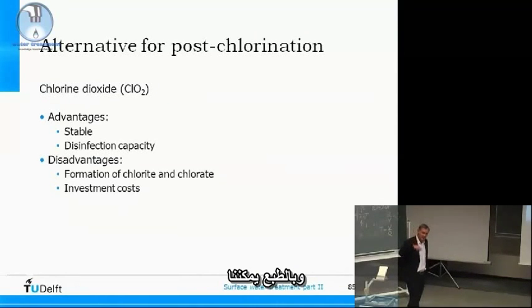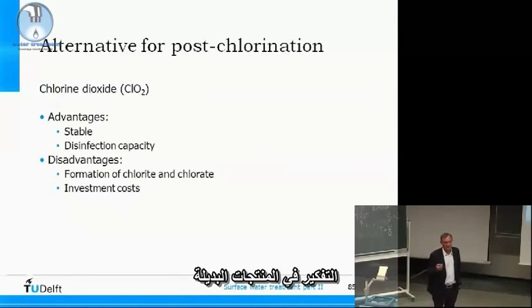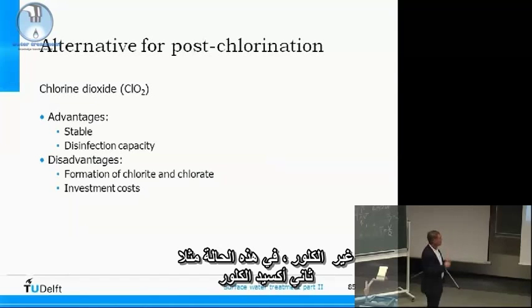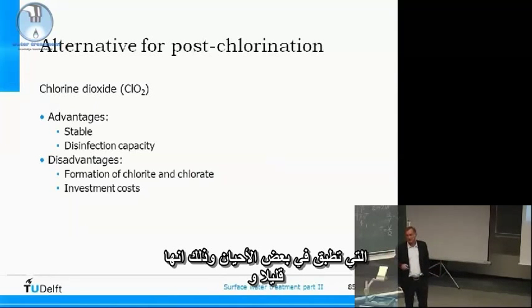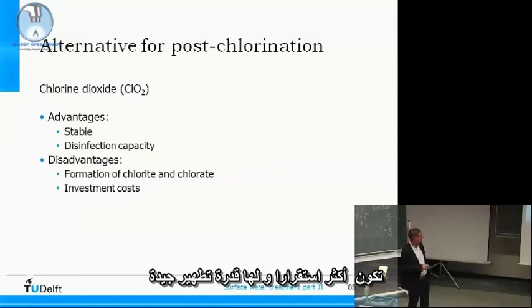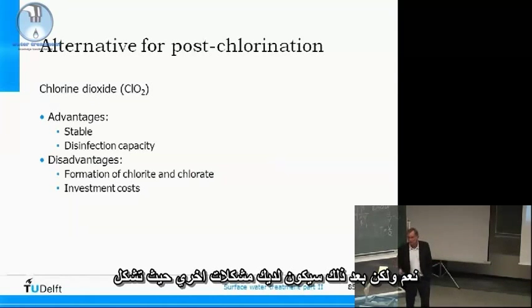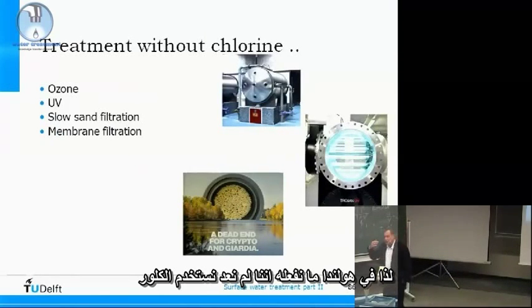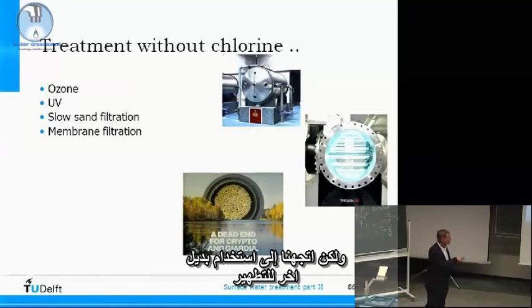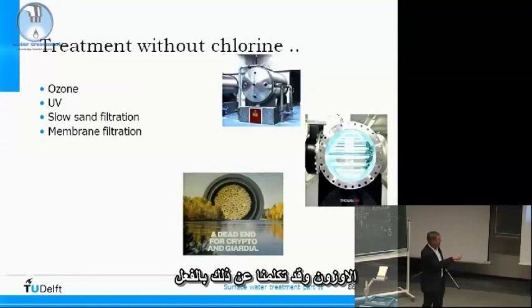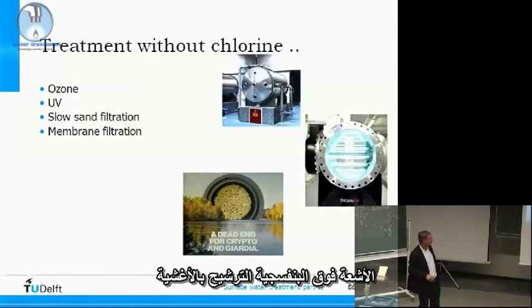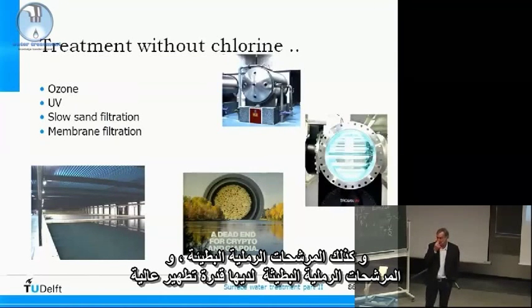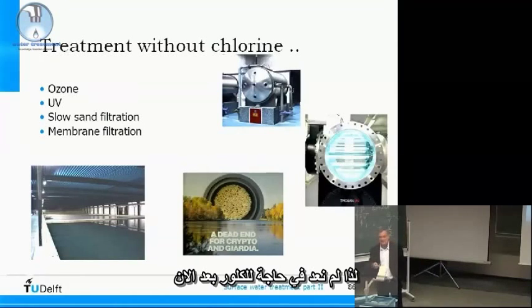There are also alternative products to chlorine. Chlorine dioxide is sometimes applied — it is a little more stable and has good disinfection capacity, but it forms chlorite and chlorate. In the Netherlands, we don't use chlorine anymore; instead we use alternative disinfection methods: ozone, UV, membranes, and slow sand filters. Slow sand filters have a high disinfection capacity, so we don't have the need for chlorine.